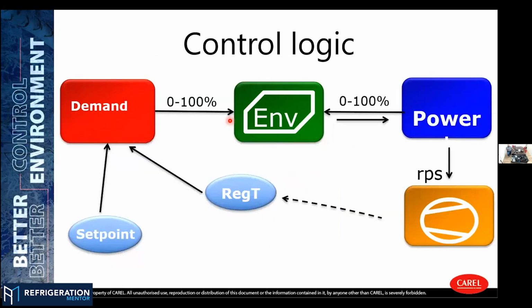Yeah, right. Thinking about the logic of the control, this is something technicians sometimes have doubts about, how it works. Generally speaking, we have the demand, which could be information that comes from the unit itself, from the application. That is basically the comparison between our set point and the pressure or the temperature that we are setting to work with that unit. That could be pressure controlled, the suction pressure, or the temperature of the ambient. So it will generate some demands or requests from the application. Once we have this information, the control will process this request and apply some filters based on the operation of the compressor.